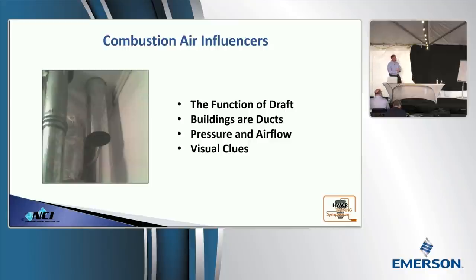So we're going to look at a function of draft, and this is where we're going to start talking about flues a little bit. What drives flues and what causes them? I want you to look at things. We're going to tie everything back to air. So I want you to look at them a little bit differently. What's crazy is you start to look at combustion air, it's the same physics that drive a duct system. There's nothing different. There's no difference in how we do this. So we're going to talk about draft, what its function is, what it does, its role, and it's really important.